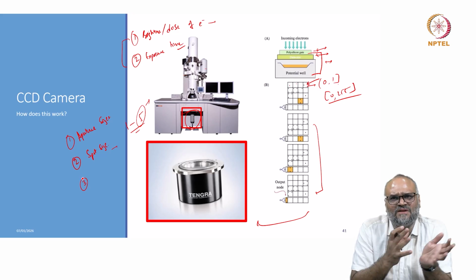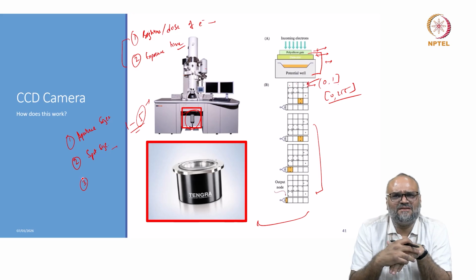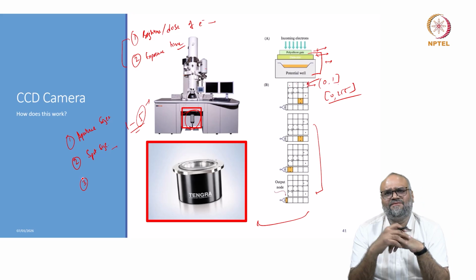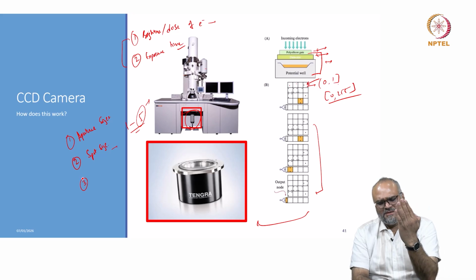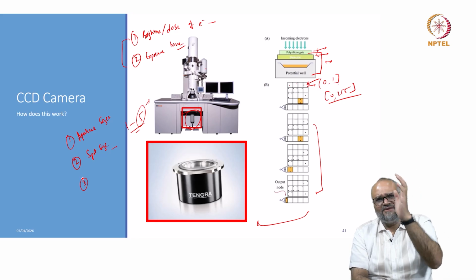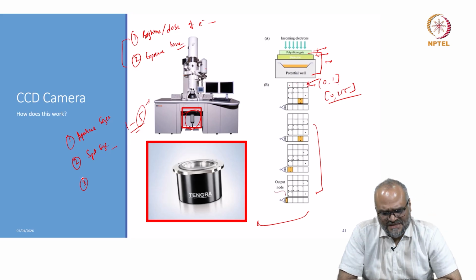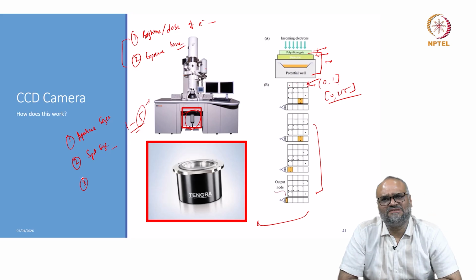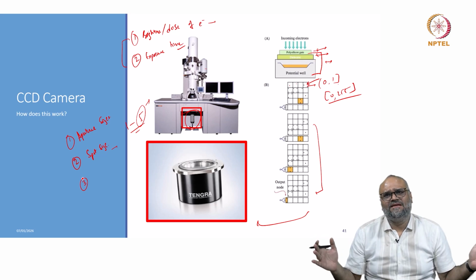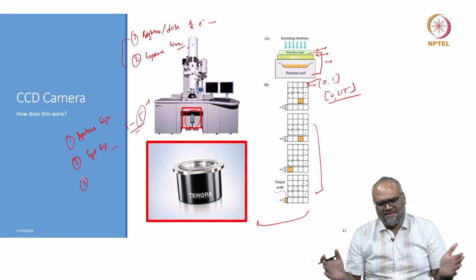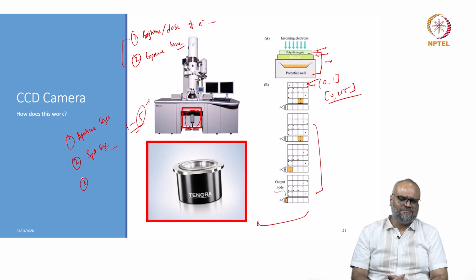Is there any kind of an image shift, or is there some physical misalignment, or so on. So identify a recognizable feature on the screen by placing an aperture halfway before you record something from the feature of your interest on your specimen, and see where it is positioned. Also check that the fluorescent screen is typically not the entire area of your detector on the CCD or CMOS camera.